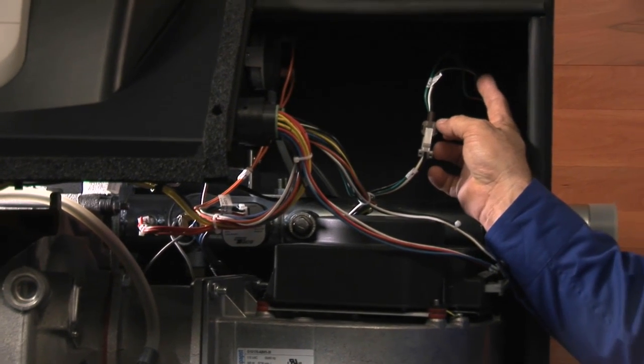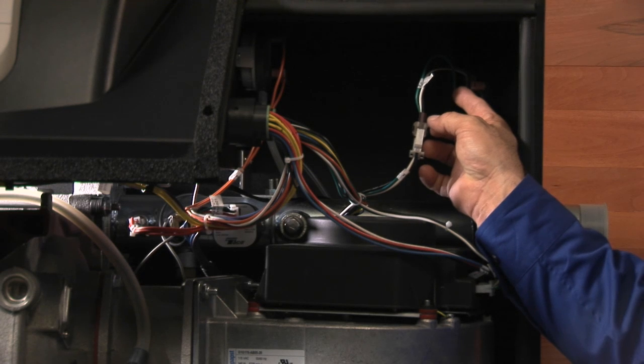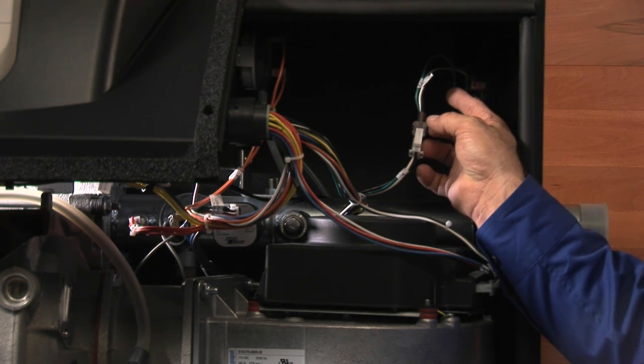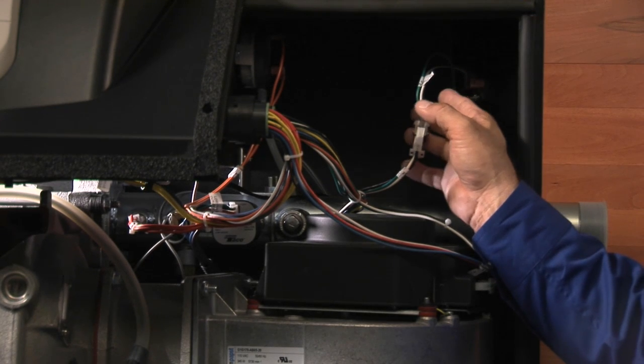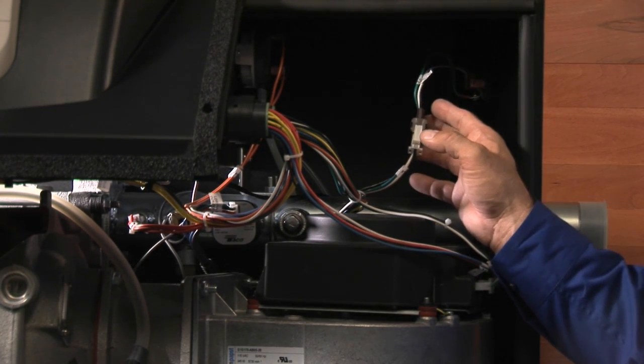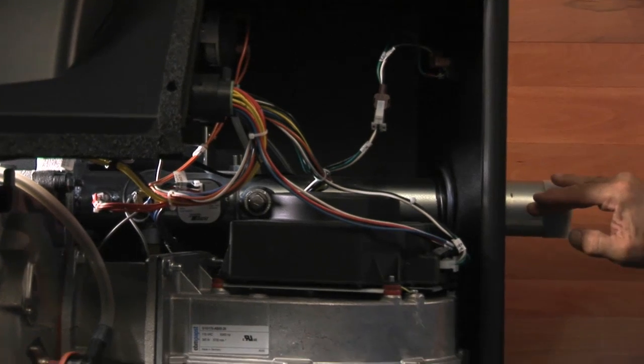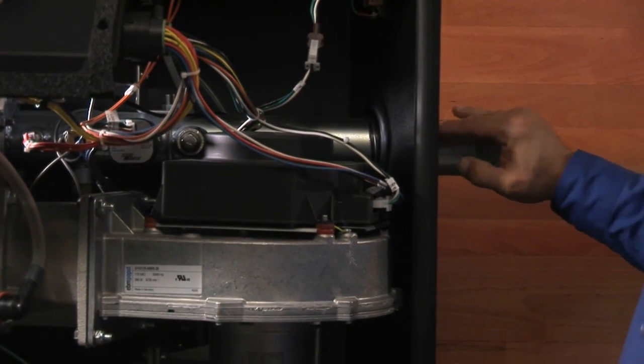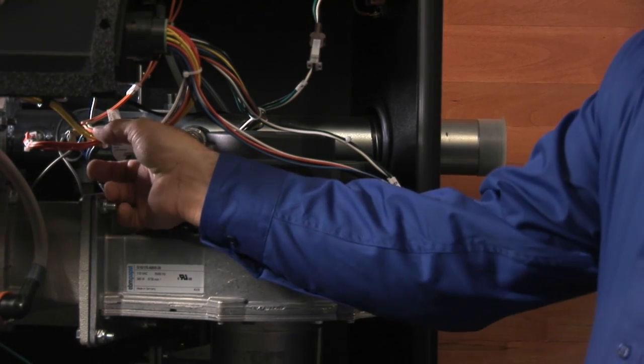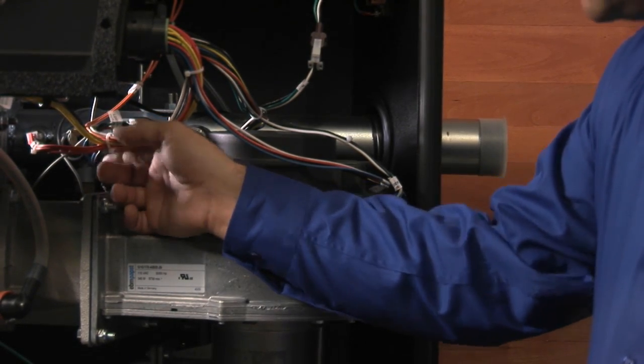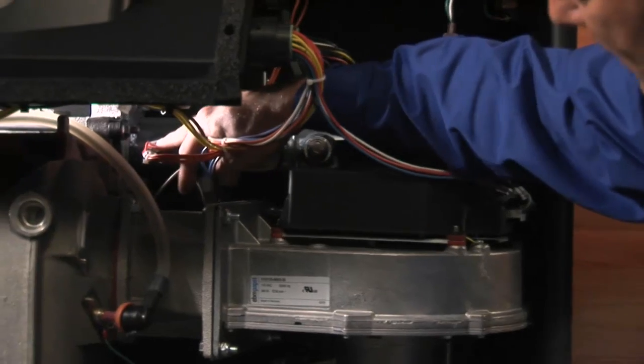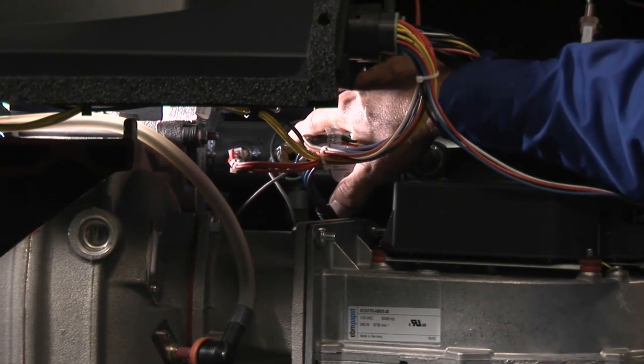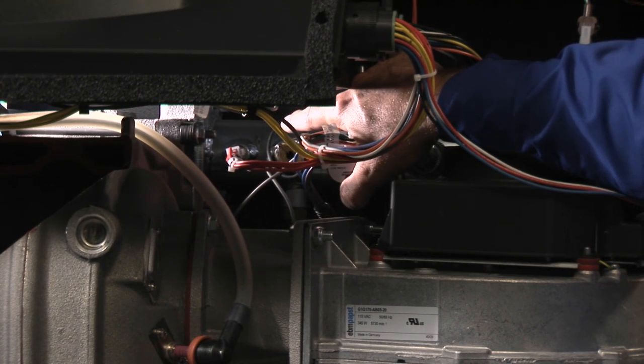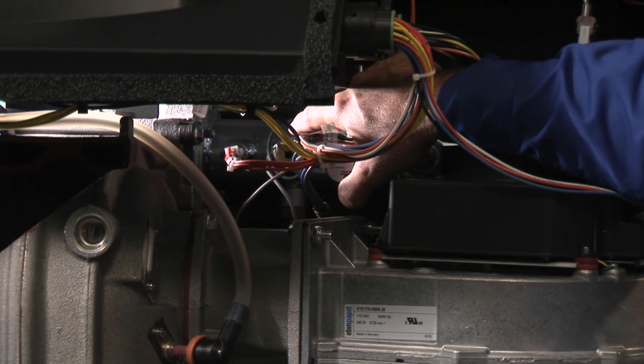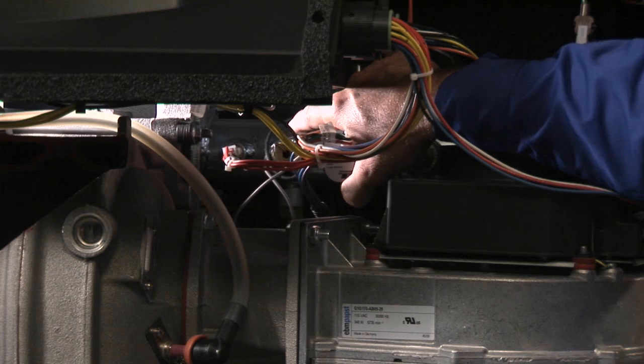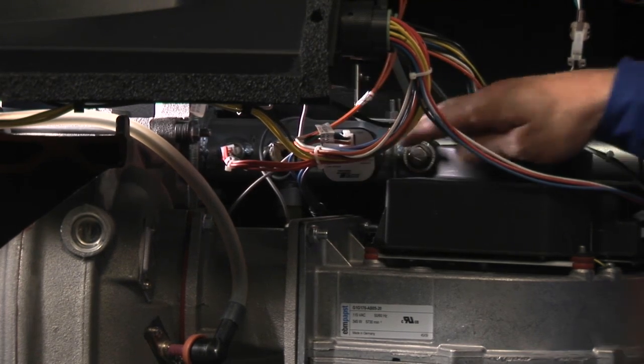There's also an outlet. All our ultra boilers, residential and commercial, have an outlet in the side of them. So if you need to plug your condensate trap or condensate pump in, you can plug it right into this receptacle. Drop down, this is the supply header on the boiler. In that supply header, the boiler comes standard with a low water cutoff. There's also a temperature sensor, and there's also the temperature and pressure port here where we transfer the information up to the display so you can see the temperature and the pressure on the boiler at all times.